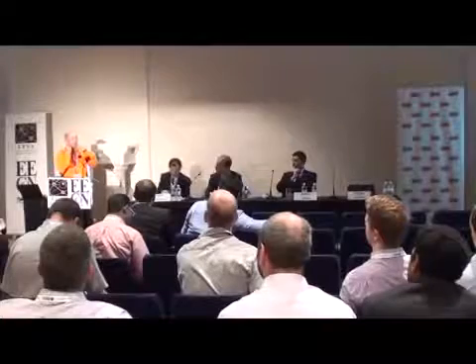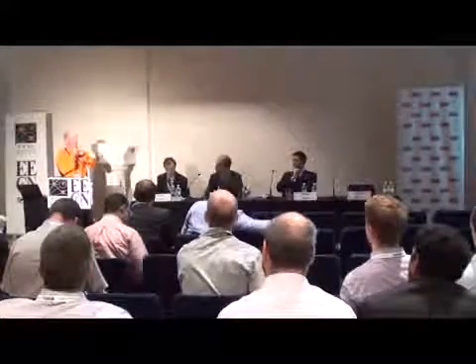Yep. Have you looked at that at all? Yeah, we have, and what we've found is the face shield with a reasonable chin cup is good, and some of your switching jackets have really high collars that will come up underneath the chin and provide fairly good protection. And once again, with the heat issues that we have in Australia, we need to take into account what we're asking our people to wear in what can be hot climates in parts of our country. So we're not looking at the balaclava from an Ausgrid perspective at the moment.